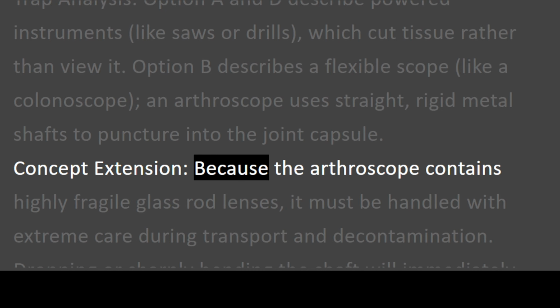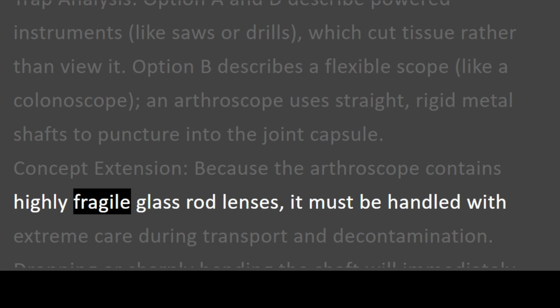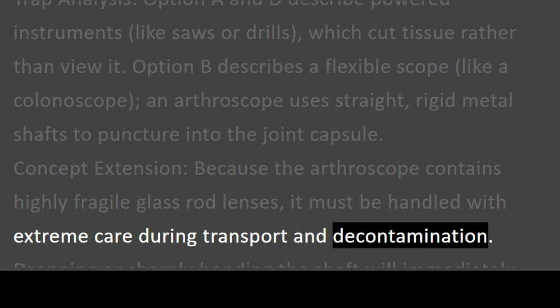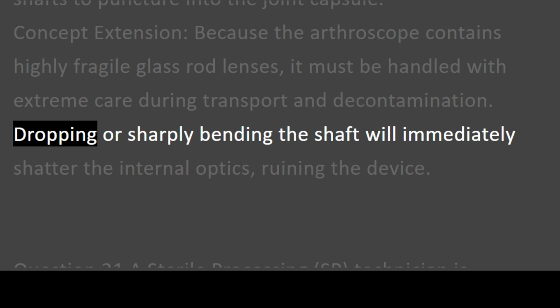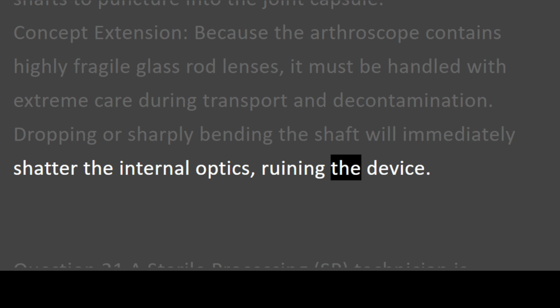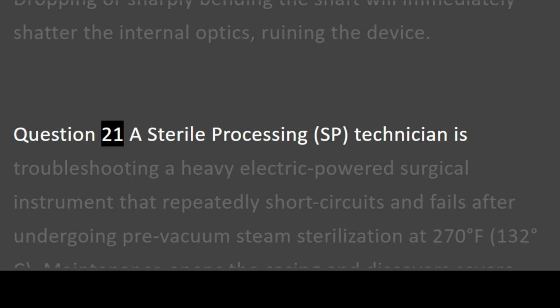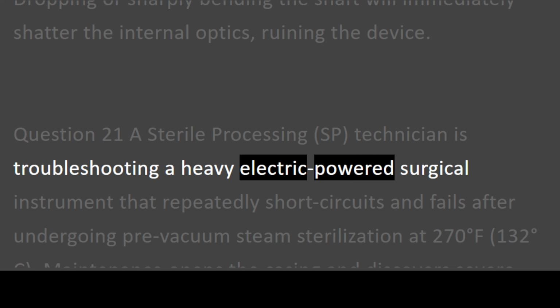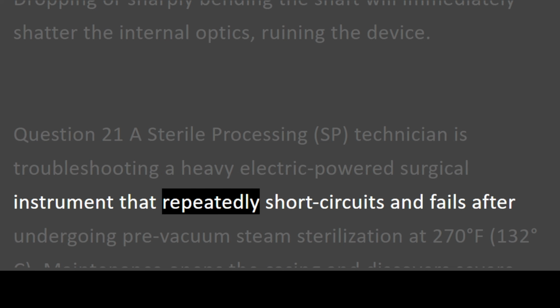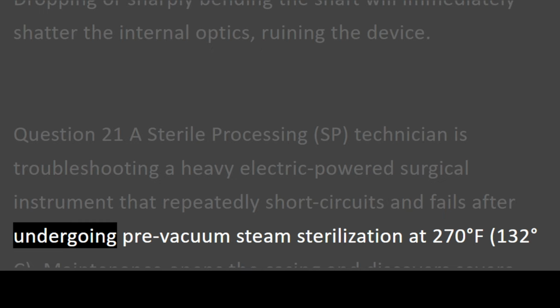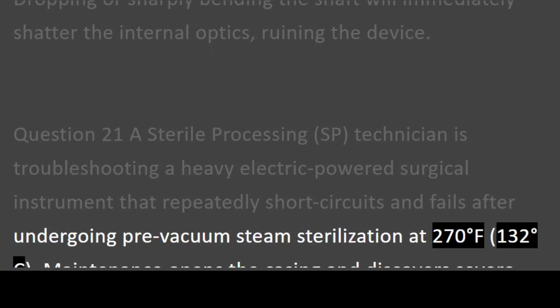Concept extension: because the arthroscope contains highly fragile glass rod lenses, it must be handled with extreme care during transport and decontamination. Dropping or sharply bending the shaft will immediately shatter the internal optics, ruining the device. Question 21. A sterile processing (SP) technician is troubleshooting a heavy electric-powered surgical instrument that repeatedly short-circuits and fails after undergoing pre-vacuum steam sterilization at 270 degrees Fahrenheit, 132 degrees Celsius.